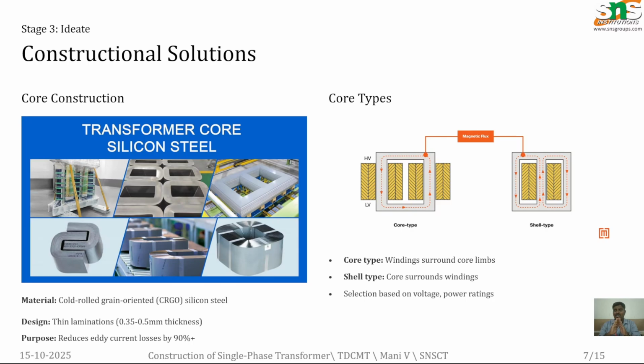The winding will surround the core limb, and in shell type, the core surrounds the winding. Okay, so the core type or shell type is chosen based on the voltage rating. If you are in need of a low power system or high power system, based on the voltage rating, we can choose either core type or shell type.